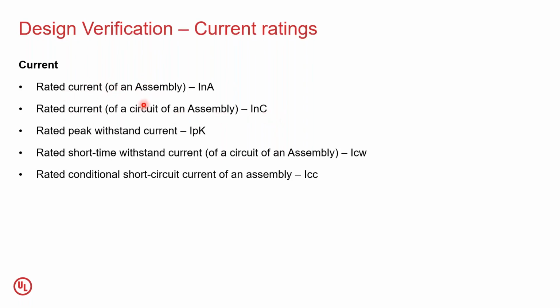After these two, you have the short circuit current ratings, which have two different contexts. One is called Icw, which is always associated with a time: the rated short-time withstand current. This could be 50 kA for 1 second, 50 kA for 3 seconds, or 50 kA for 2 seconds. So it is always associated with a time. Quite naturally, when you have a short-time withstand current, there is always a peak associated, because the RMS value will have an initial peak, and that is called the rated peak withstand current.